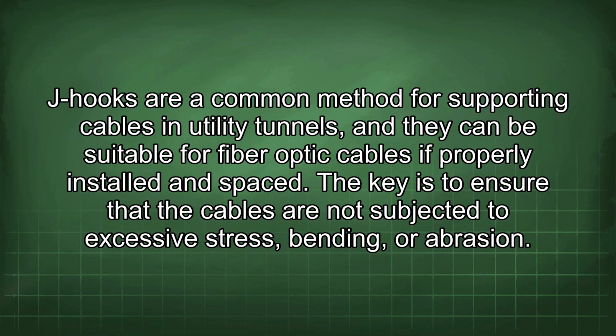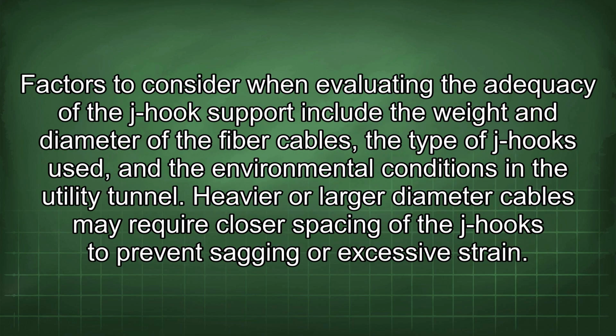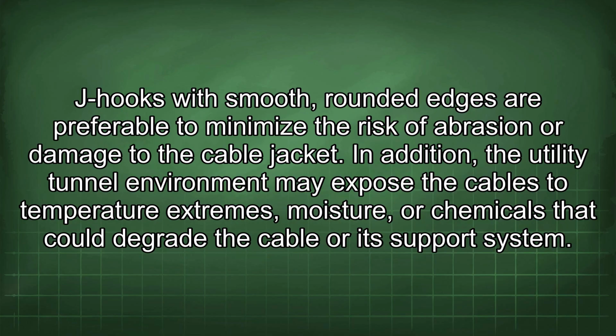J-hooks are a common method for supporting cables in utility tunnels, and they can be suitable for fiber optic cables if properly installed and spaced. The key is to ensure that the cables are not subjected to excessive stress, bending, or abrasion. Factors to consider when evaluating the adequacy of the J-hook support include the weight and diameter of the fiber cables, the type of J-hooks used, and the environmental conditions in the utility tunnel. Heavier or larger diameter cables may require closer spacing of the J-hooks to prevent sagging or excessive strain. J-hooks with smooth, rounded edges are preferable to minimize the risk of abrasion or damage to the cable jacket.